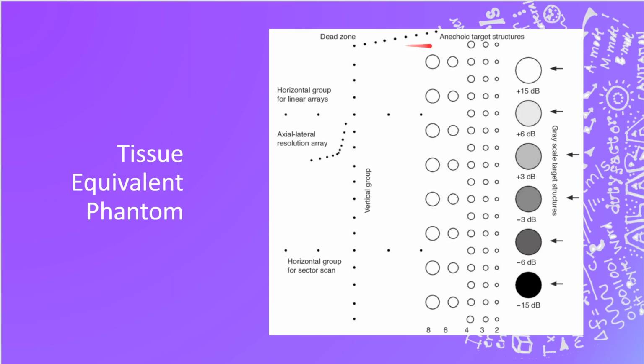So on your picture, once you put the probe down, if you cannot see 1, 2, 3, 4, 5, 6, 7, 8, 9, there are 9 pins. Those 9 pins, if you can't see all 9 of them, it tells us where the dead zone is. So maybe you can only see down from pin number 4 and on. That would mean that we're missing this first little bit up here. So the dead zone tells us how much of that near field we are actually missing.